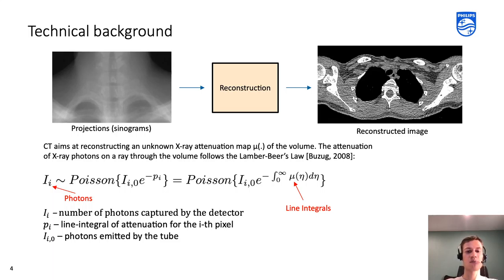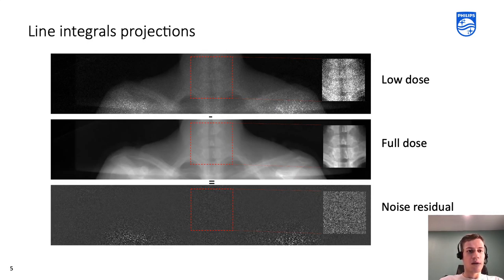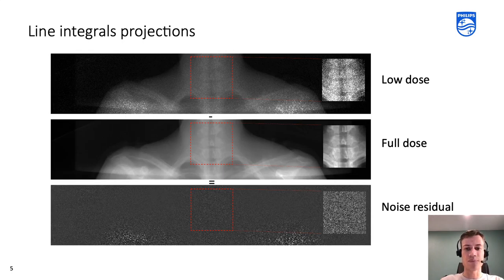I would like to explain a few technical details. A CT scanner captures projections and not the images — the reconstruction step converts projections into images. Traditionally, denoising is done in the image domain. However, projections are more promising because they contain redundant information, which is beneficial for denoising. In addition, some artifacts of images, such as streaks, are almost impossible to remove in the image domain and are better removable in projections.